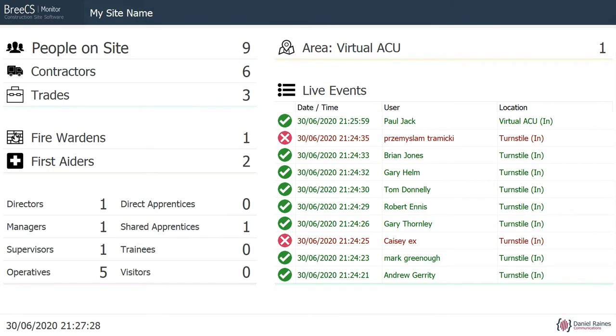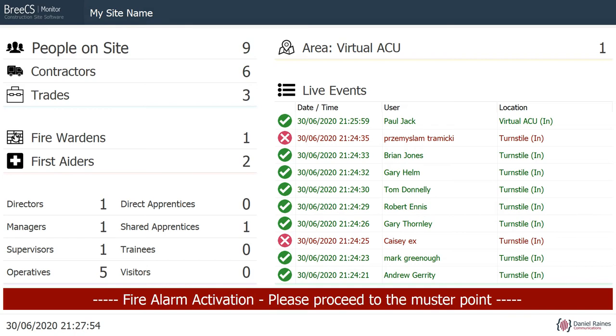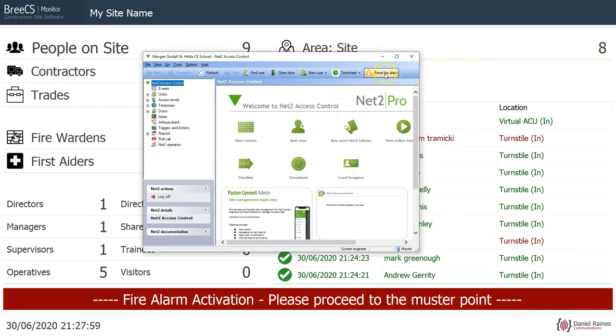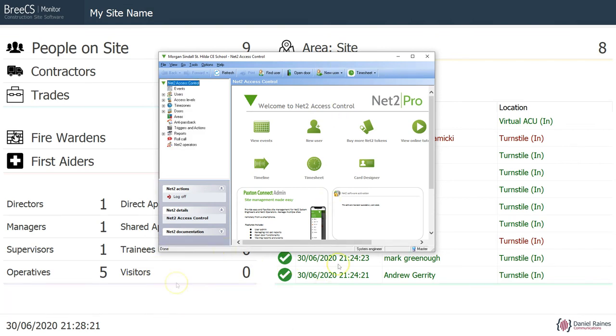In addition, within Net2 itself, if you wire a fire alarm or some form of mushroom button into one of the Net2 ACU inputs and program it as a fire alarm input, you'll get the same effect. Within a few seconds we're going to get the notification again that the fire alarm has activated, and as we can see we've got the 'reset fire alarm' button. In this example I've got the tamper switch programmed as 'set as fire', and it's also programmed as self-resetting, so as soon as I push the button again it will auto-reset and the message will disappear.